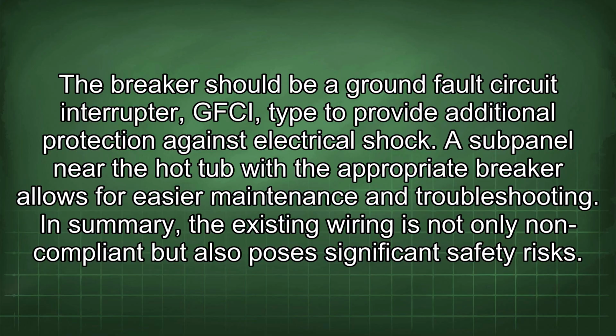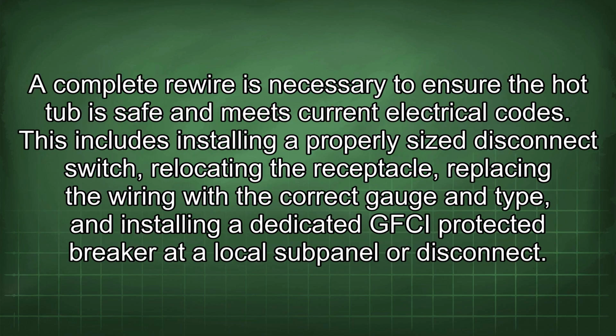In summary, the existing wiring is not only non-compliant but also poses significant safety risks. A complete rewire is necessary to ensure the hot tub is safe and meets current electrical codes. This includes installing a properly sized disconnect switch, relocating the receptacle, replacing the wiring with the correct gauge and type, and installing a dedicated GFCI protected breaker to a local sub-panel or disconnect.